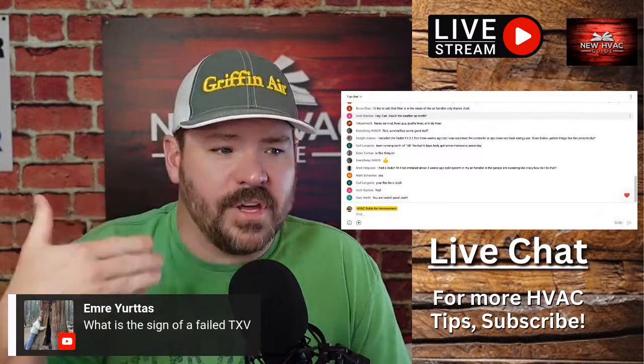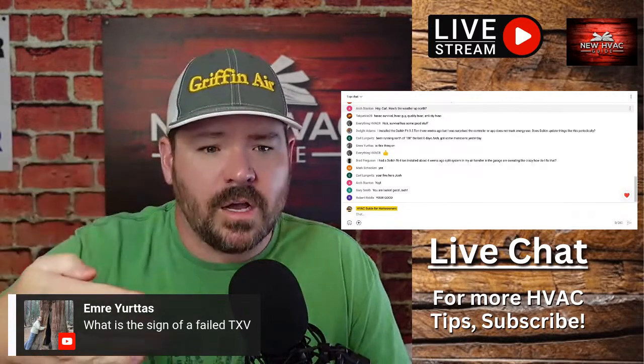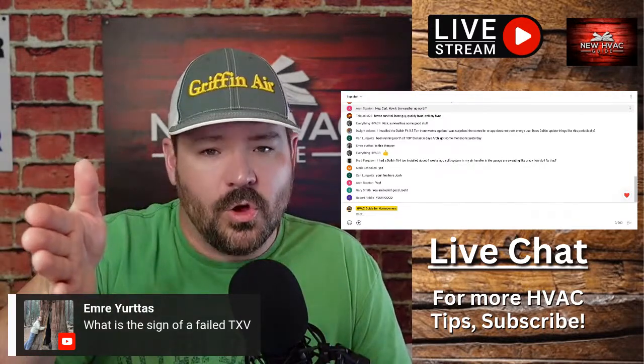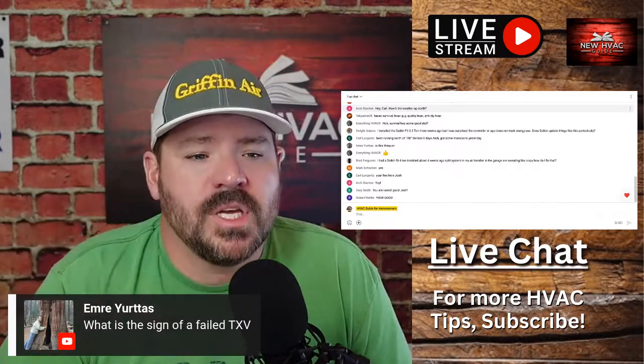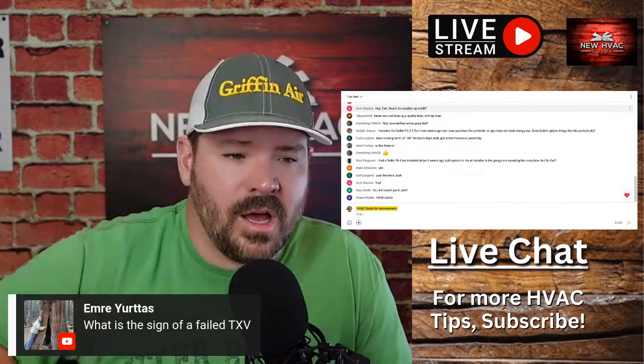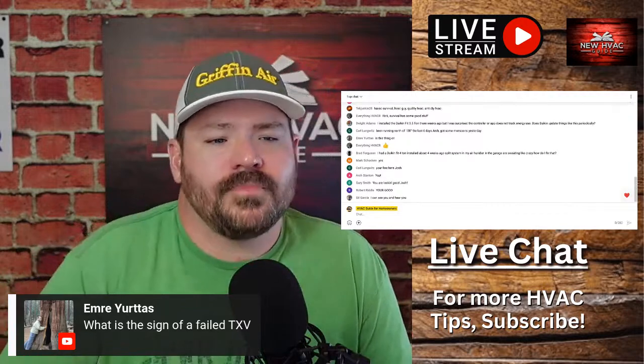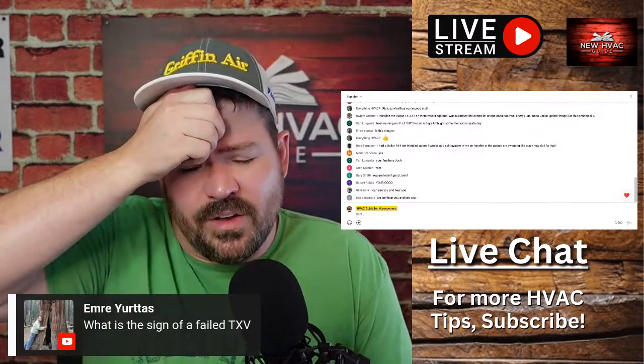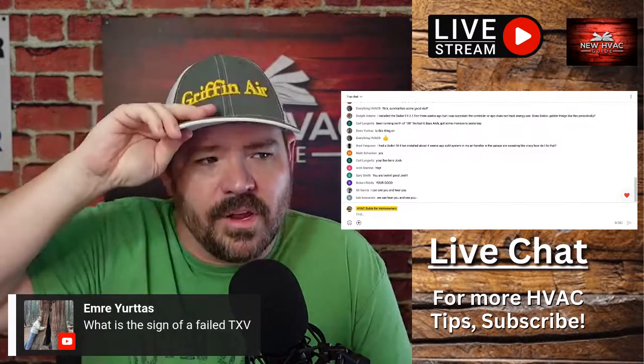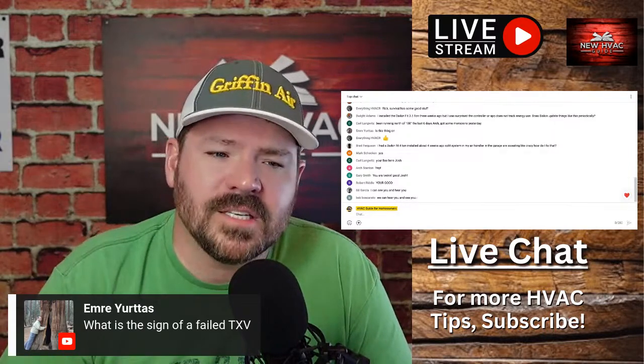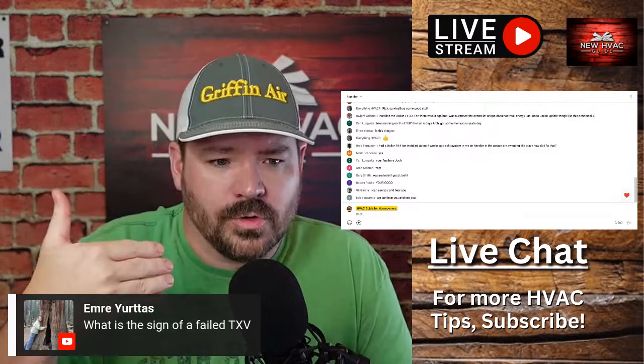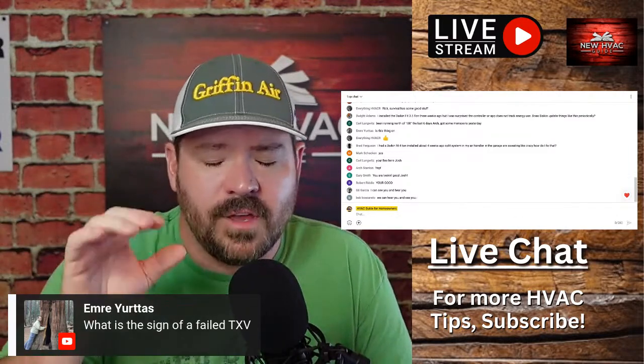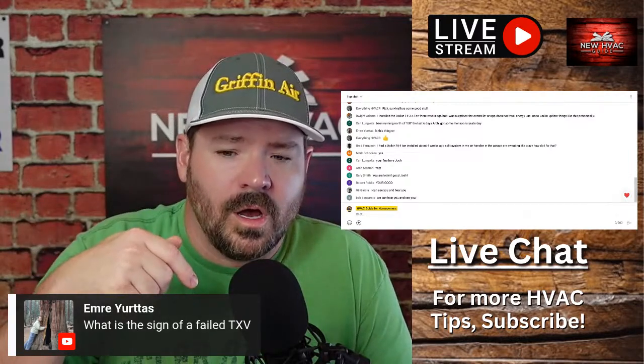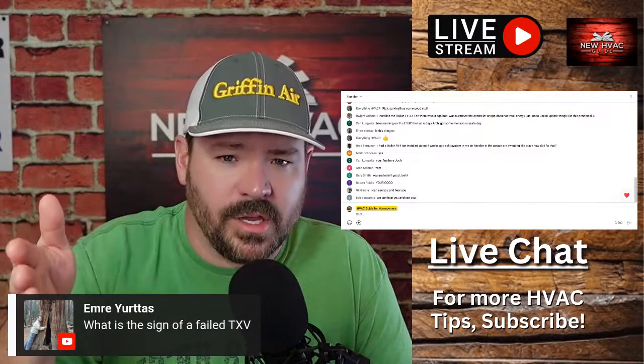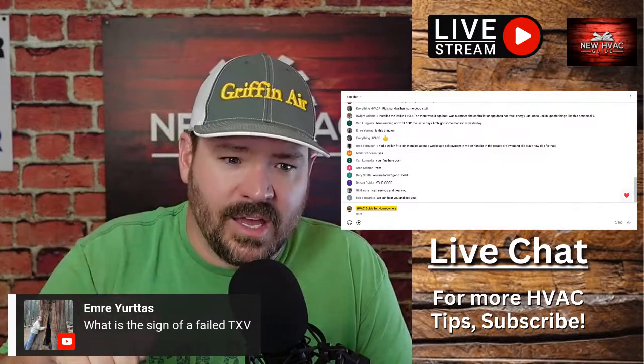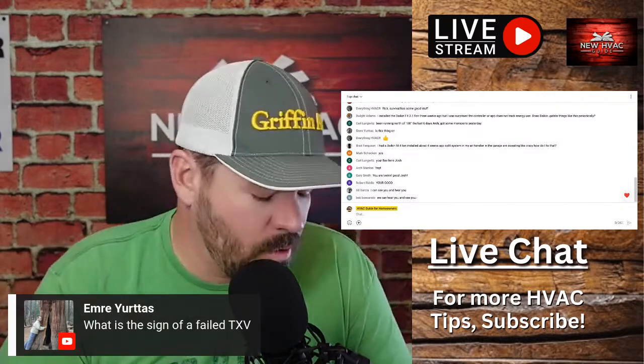So Emery asked, what's the sign of a failed TXV? A TXV is essentially a valve that opens and closes. Some TXVs will become stuck - some stay open and don't open and close, some stay closed and don't open, and some have a temperature bulb that's not acting properly. The majority of failed TXVs I see just become stuck in some manner, creating some sort of restriction, although I have seen some stay open or closed. A good way to test that is if you take the system and reverse it. The indoor TXV in heating mode should be completely open, and the outdoor TXV in cooling should be completely open, so that it can flow refrigerant that way.